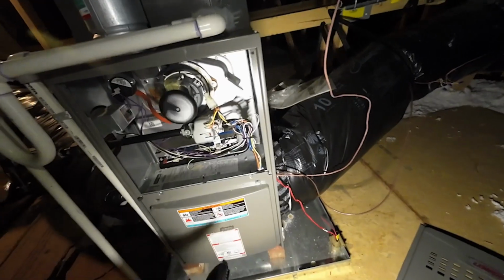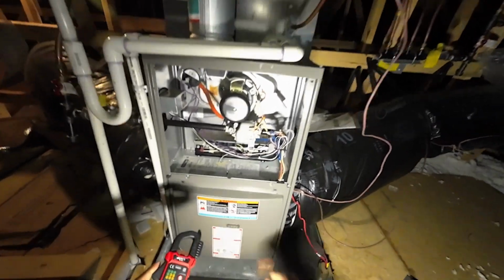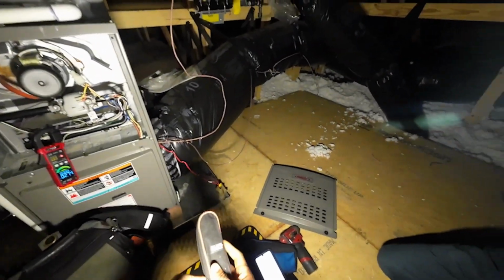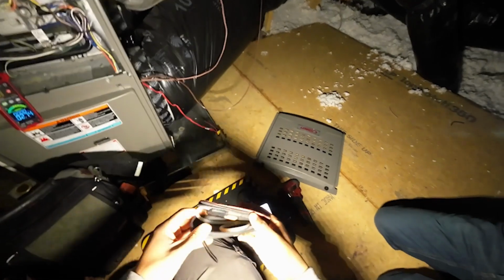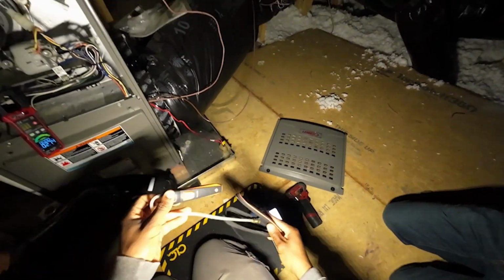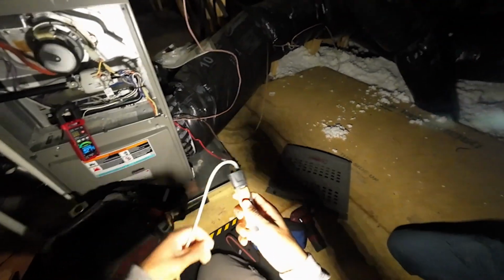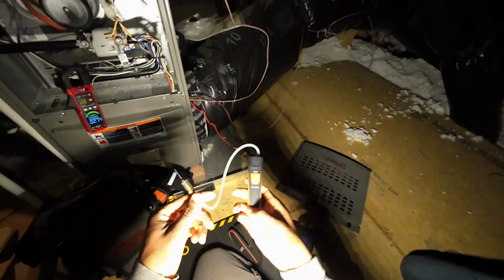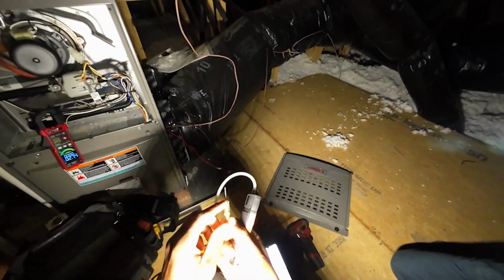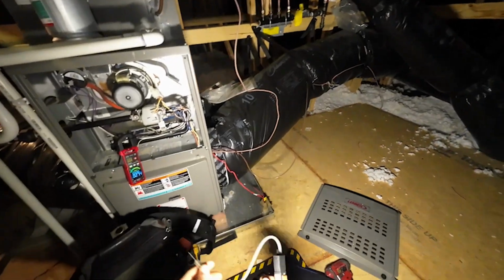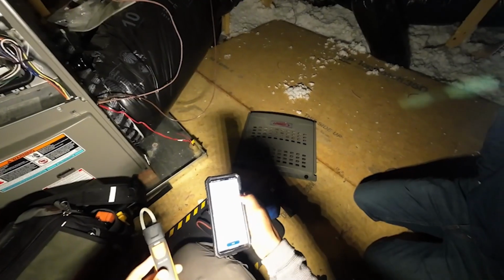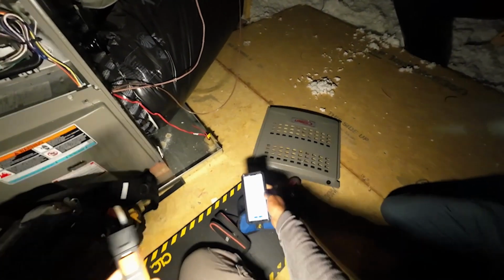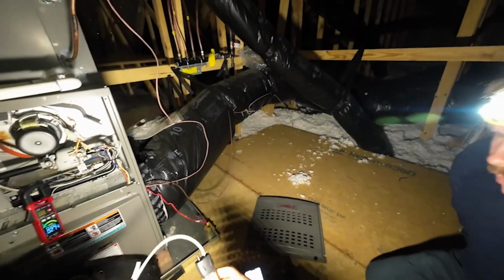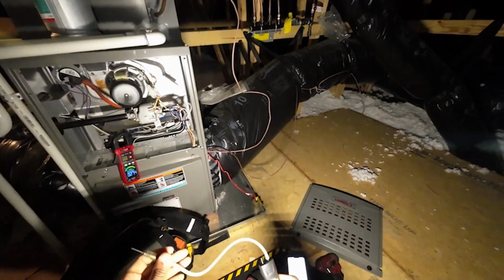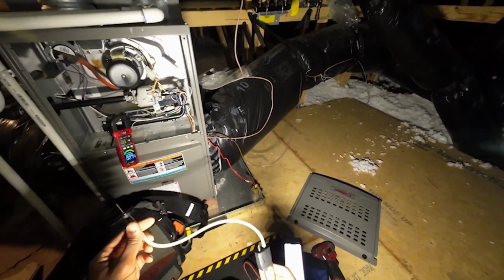0.48, yeah, 0.48, thanks, from, I've got what we call a manometer. You got any experience with this? It's the static pressure. Yes, sir. And yep, we could do gas pressure, static pressure. So essentially, I've got this here tip on here with the ball inflator. So I don't have to now drill any major holes in this thing. I can pretty much say zero it out. You always want to zero manometers to atmosphere. That means it's nulling any background, any pressures as it's in the atmospheric pressure.